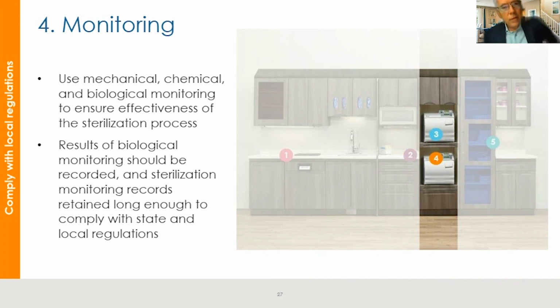The CDC says you should use mechanical, chemical, and biological monitoring to make sure sterilization is effective. With mechanical, we're talking about gauges, temperature gauges, timers, pressure indicators. Let's face it, most of us don't have a chance to sit there and watch that all the time. But we certainly look at chemical indicators, the heat indicators, so we know those instruments have been processed. And of course, the spore monitoring.